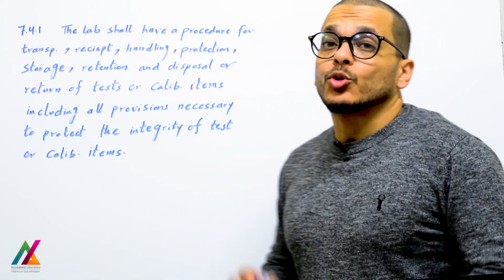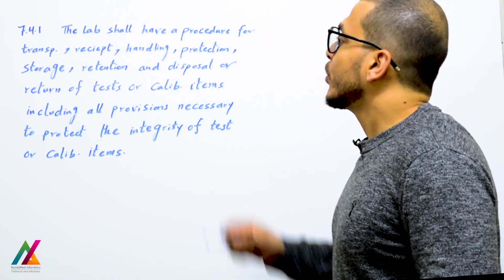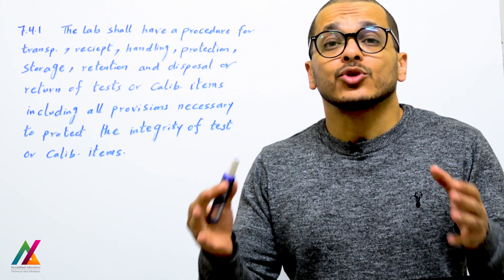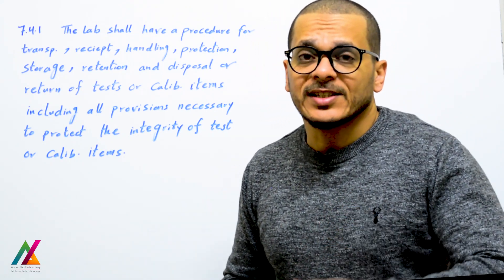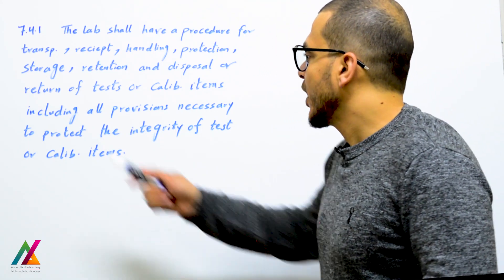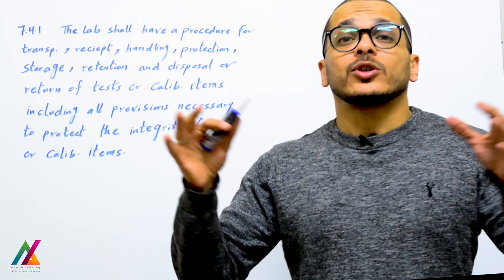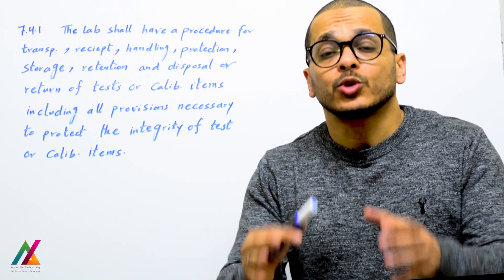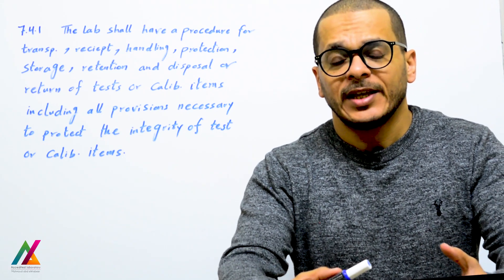For calibration laboratories, the lab shall have a procedure — it is mandatory — for transportation, receipt, handling, protection, storage, retention, and disposal or return of test or calibration items. You will prepare a procedure including all of these points to protect the integrity of the sample up to receipt in the lab and subsequent handling to ensure the integrity of the results.